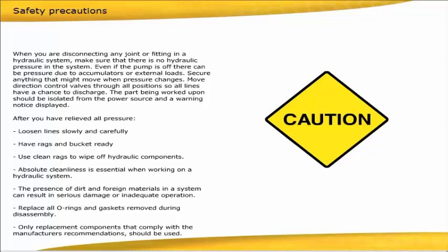Have rags and bucket ready. Use clean rags to wipe off hydraulic components. Absolute cleanliness is essential when working on a hydraulic system. The presence of dirt and foreign materials in a system can result in serious damage or inadequate operation. Replace all o-rings and gaskets removed during disassembly. Only replacement components that comply with the manufacturer's recommendations should be used.